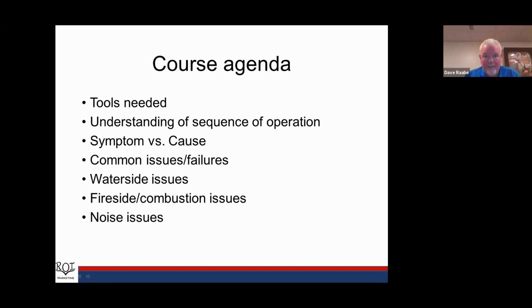So the agenda, we're going to go over the tools that you'll need, understanding of the sequence of operation on boilers, a little something called symptom versus cause, and I'm going to go over some common issues and failures that you can run into on condensing boilers. Then we'll talk a bit about water side issues, and then fire side or combustion issues, and lastly about noise. And then I've got a little bit of work on the website that I want to show you. US Boiler has a pretty neat troubleshooting tool available to contractors.